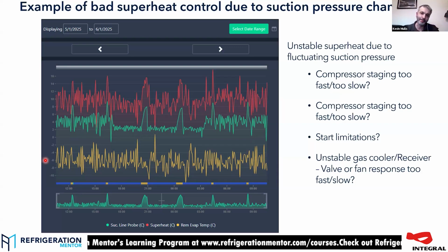You're then waiting for another machine to start. And the flip side happens if you're too slow. The valves are all creeping open. The suction pressure can't respond quickly enough. When it does come on, it needs too much duty. It ends up pulling it down too fast.